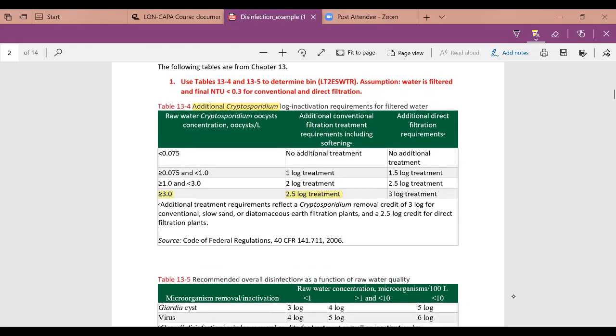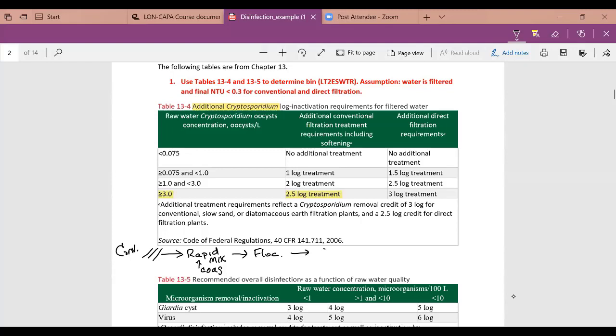We have two treatment types: conventional filtration and direct filtration. For conventional treatment, you start with screening, then rapid mix with coagulant, flocculation, sedimentation, and filtration. Direct filtration — used for very pristine waters like Lake Superior — typically has screening, possibly coagulant addition, and filtration directly.